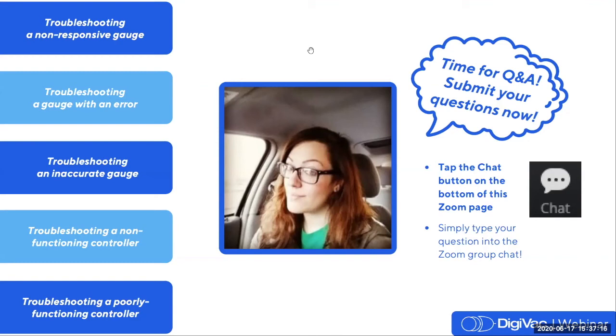Now, what we're really looking for is not so much exactly a resistance measurement within a certain range, but to see that they're electrically connected in the first place. Around 1.5 to 2 ohms happens to be the standard, but what we're really looking to find out is whether we've got an open loop between any one of those pin combinations. But this is a great observation that should absolutely be stated. It's very important, of course, to figure the resistance of your leads into whatever measurements you're trying to take with your meter.